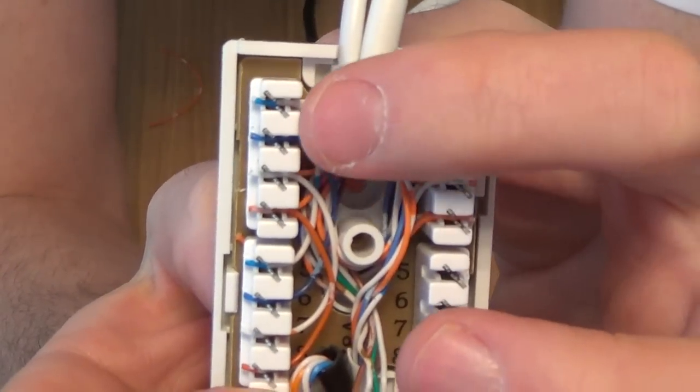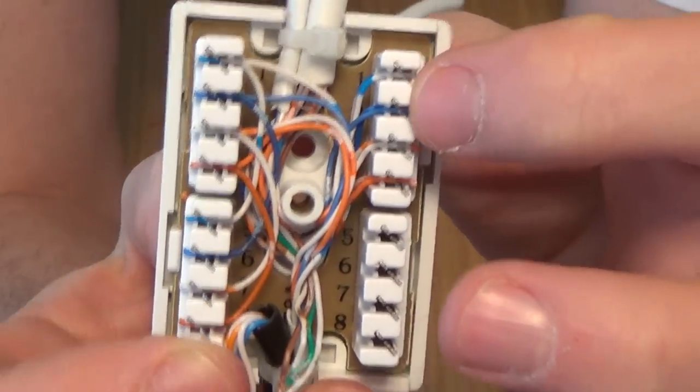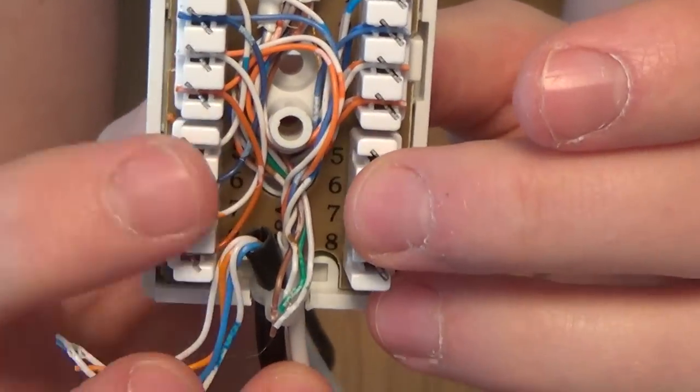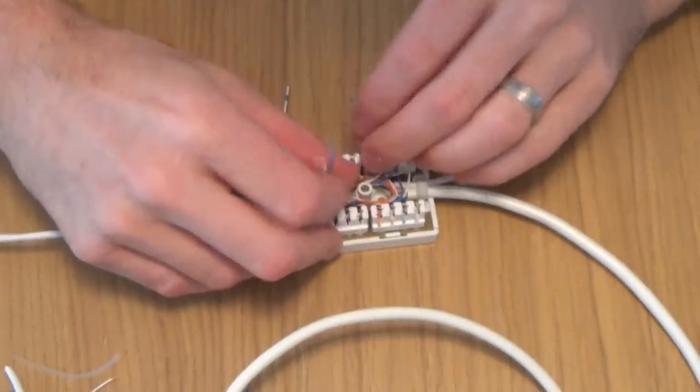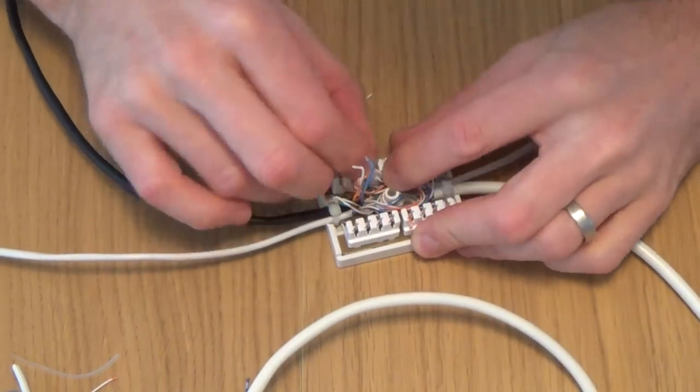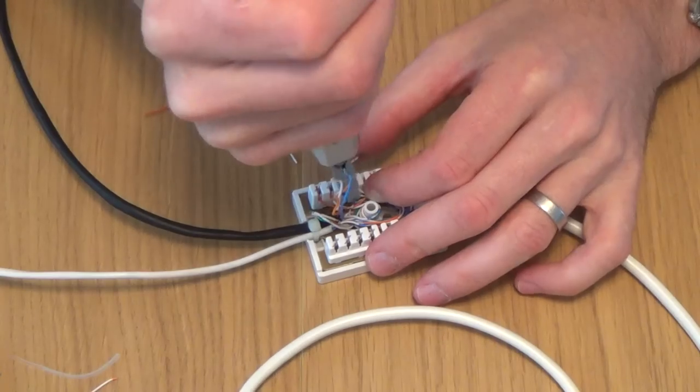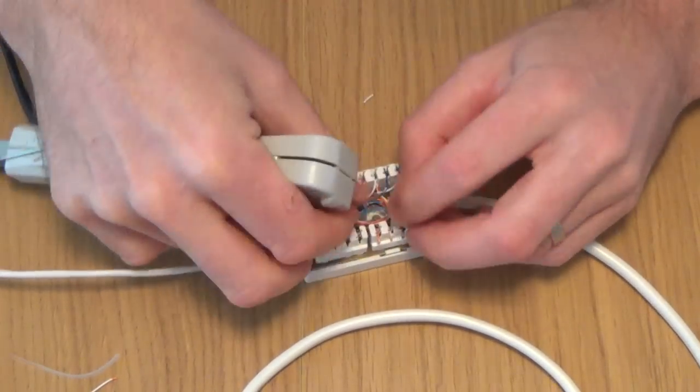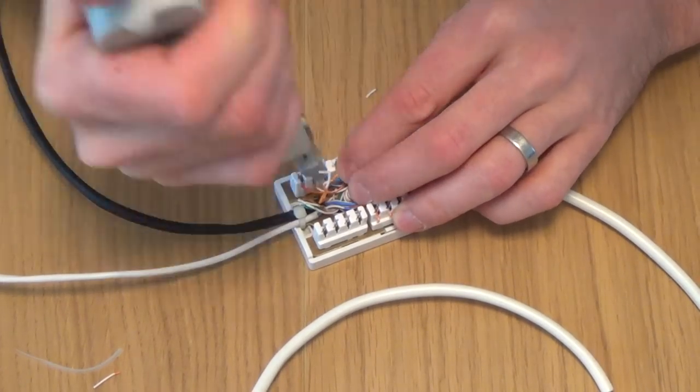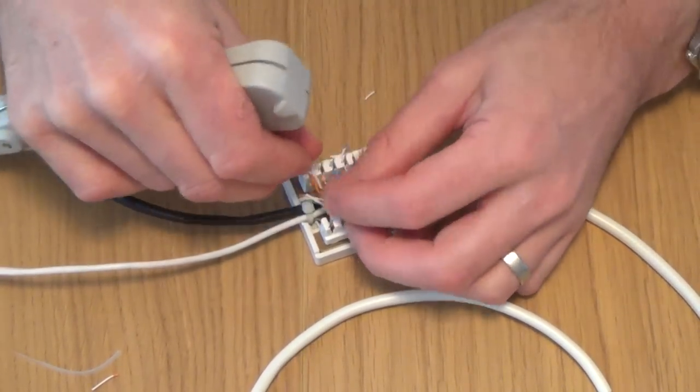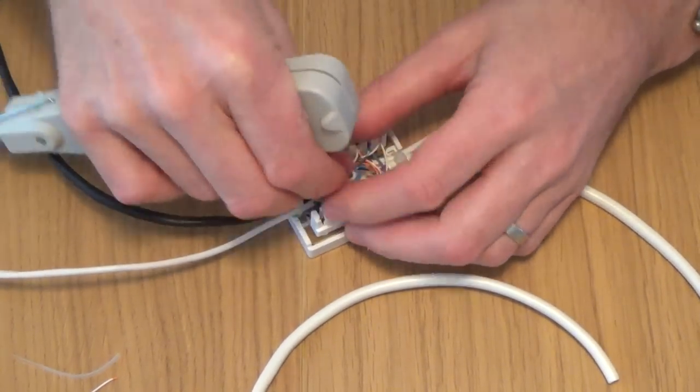So now as you can see, we've got the main cable coming in. It's livened up, for example, if we're talking about the blue pair, it's livened up one, two to one, two here. But now we've also livened up five, six down here. So now these terminals here have become three, and this one here. So we've got to reconnect our original wire. So we're just reconnecting the original wire. Obviously if you're doing this from start, you'll have a bit more room than me, because I've already terminated the wires. That's the idea of leaving slack, you see.